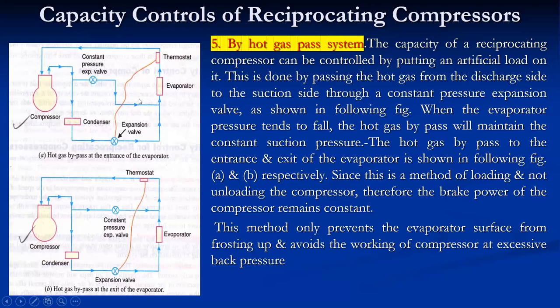If the defrosting mechanism is already available, the same mechanism can be used for capacity control of the compressor. However, there is no power saving with this method — the compressor extracts the same power as at full capacity. It is only recommended when load fluctuation is 10–15%; for variations more than 30–40%, other mechanisms should be adopted. This method only prevents the evaporator surface from frosting up and avoids the compressor working at excessive back pressure.